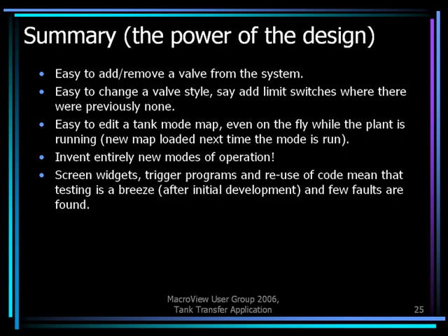The new map will only be loaded next time that the thing is running, so you can mess with the whole map system while the actual plant's in operation. You can invent entirely new modes of operation, and the PLC doesn't even have to know about them, as long as the map supports it. And we're using screen widgets, trigger programs, and code reuse, meaning that testing is done once, and then obviously we do test it, but we don't expect to find any faults.